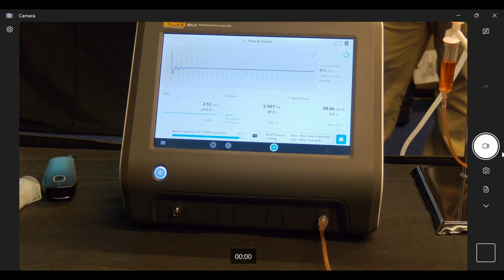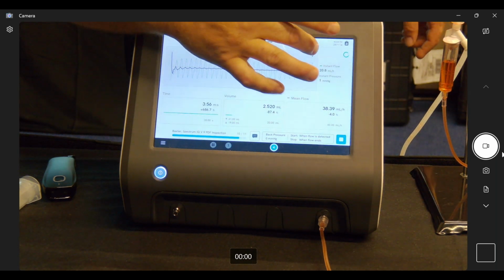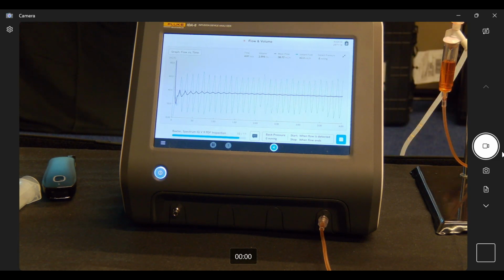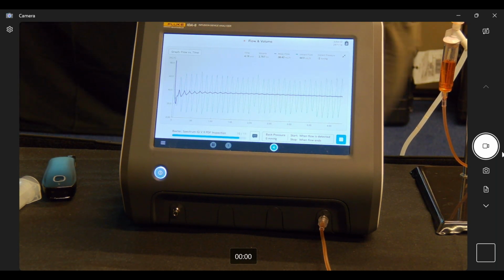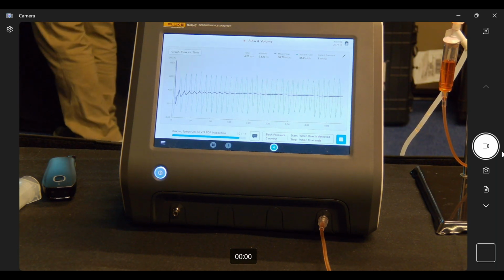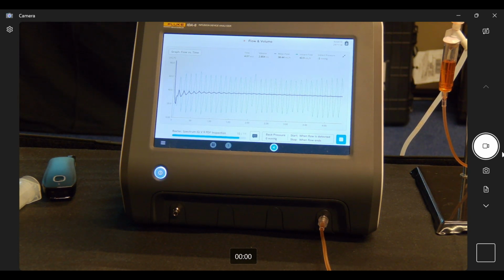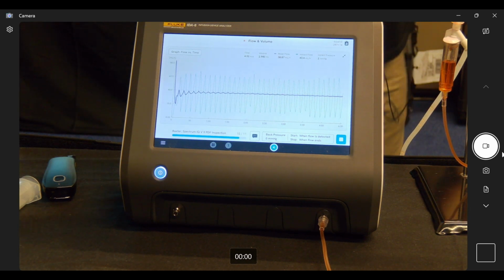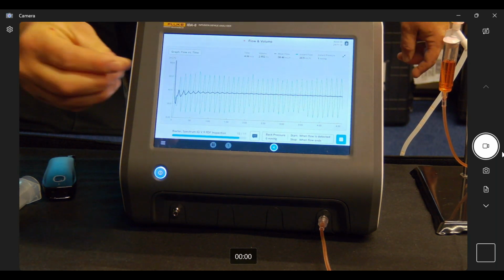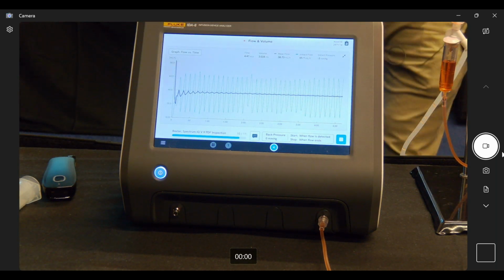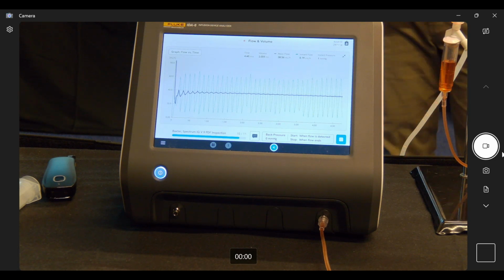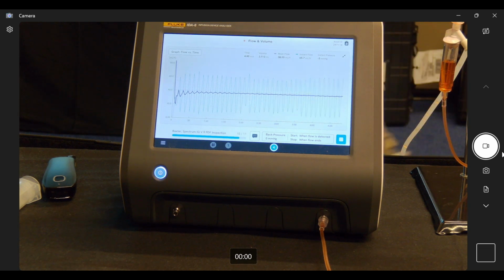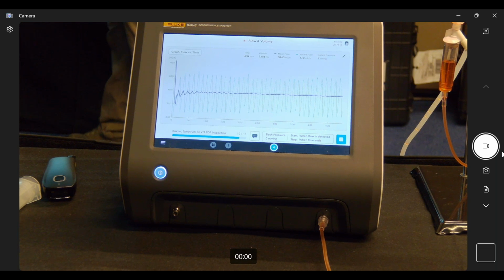So what's really neat about this screen is, I'm going to zoom in here for a second. If you watch this, you're going to notice something. This is my instantaneous flow across the bottom, and you see what happened here, and here, and here. Something's wrong with this IV pump. What's interesting is my flow has maintained; my mean flow is 38.7. So my mean flow is still within tolerance, but there's something happening here. If I wanted to, I could click on my screen and see, at the exact point in time, what my peak flow was and what my time was. I actually know the issue. This is an older IV pump. I have a bad finger in it. It needs to have some silicone put in it. But my point is, you can actually hear it grinding. You can now look at your outputs and see exactly where you have any peaks or valleys.